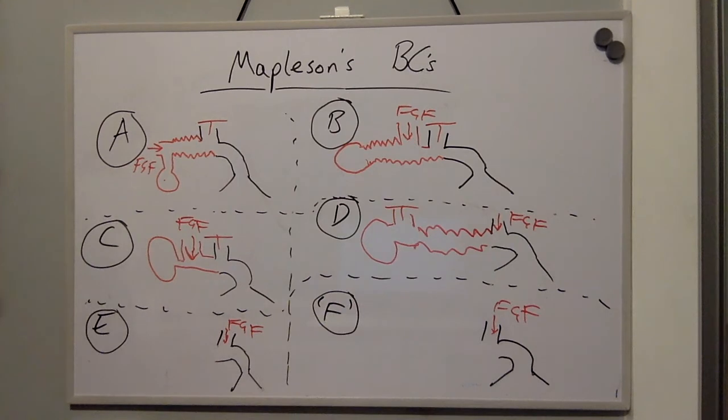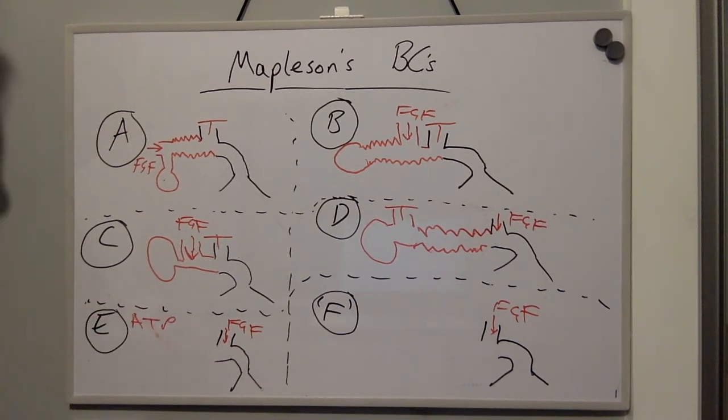Here's the long tubing. We then have the pressure control valve here and the reservoir bag. E is an Ayre's T piece and it's commonly used in paediatrics because it provides little resistance to gas flow.